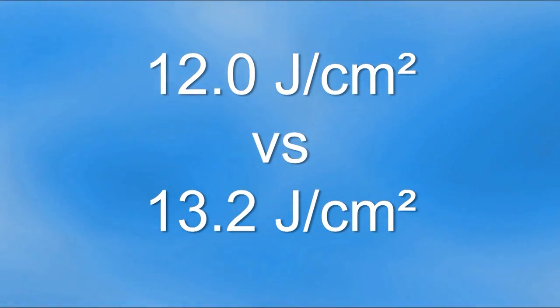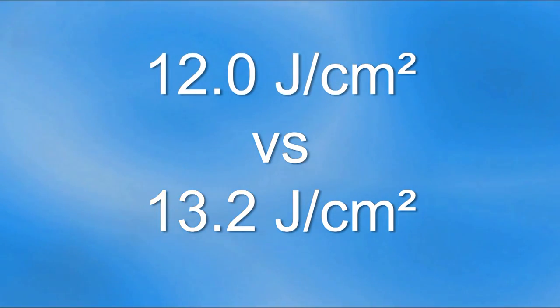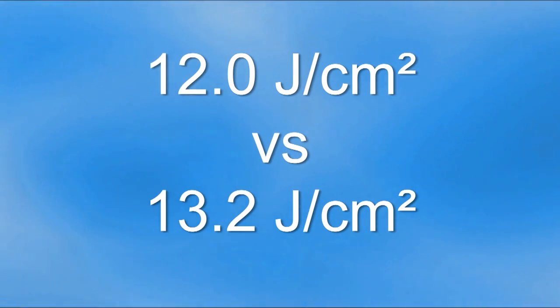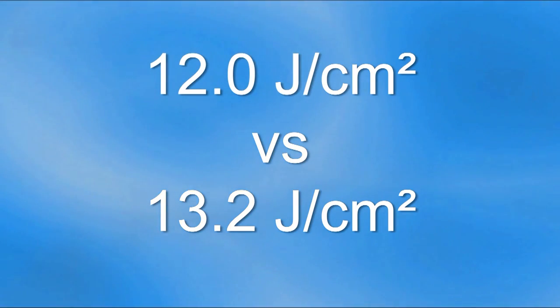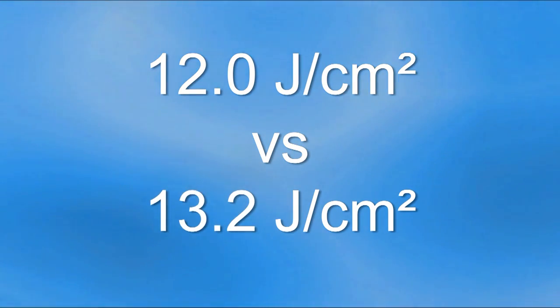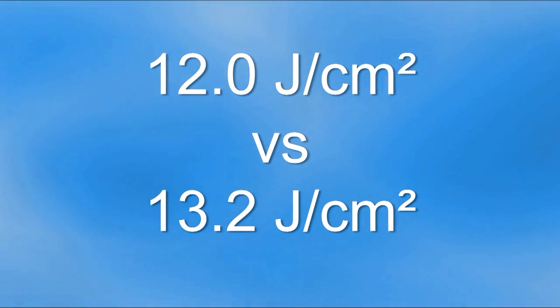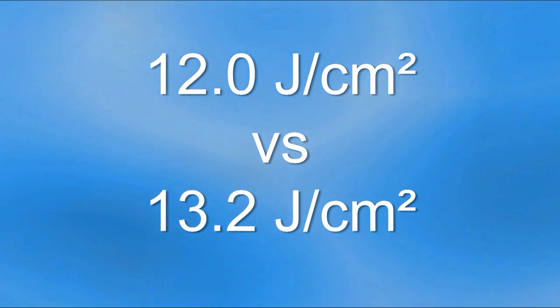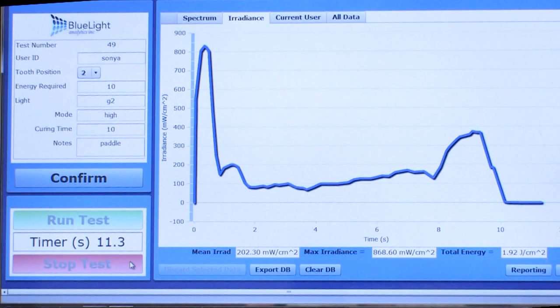The operators in the last two clips were both demonstrating good light curing technique. They were wearing eye protection, they were watching and paying attention to what they were doing, and they both used the same light on the same tooth. In both cases, they delivered more than 10 joules, but there was a difference of approximately 10% between the two operators.